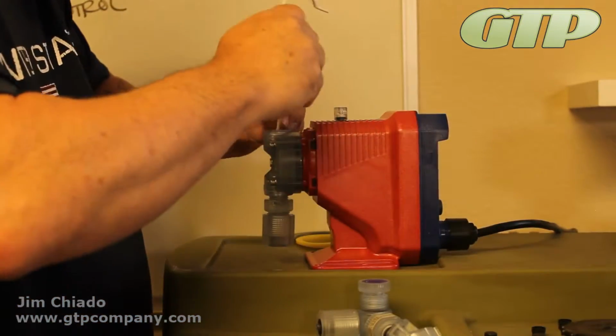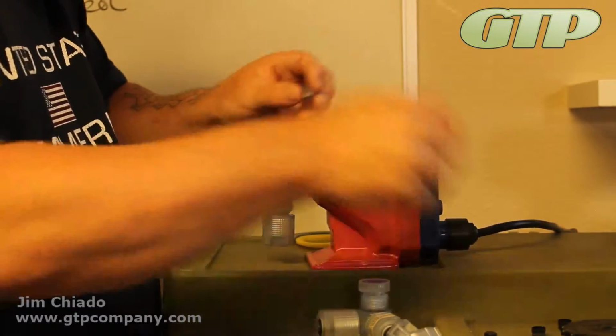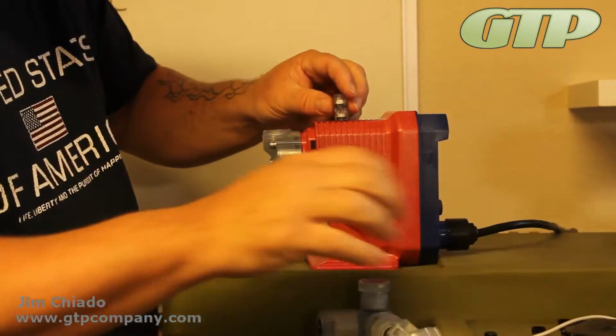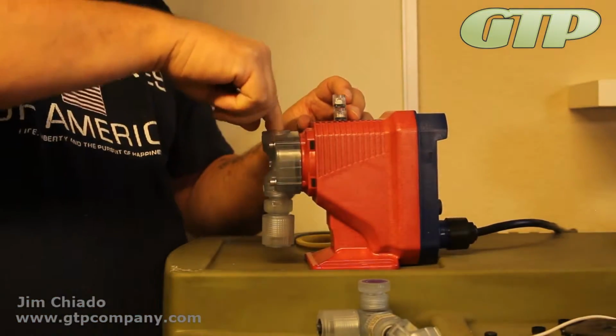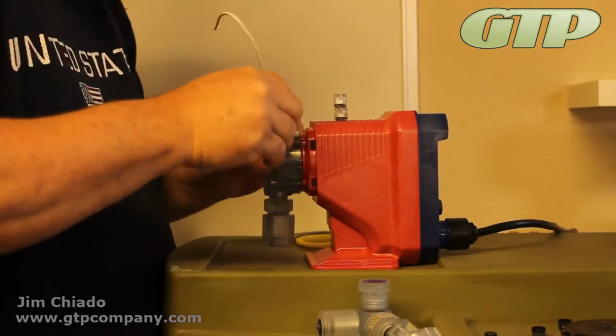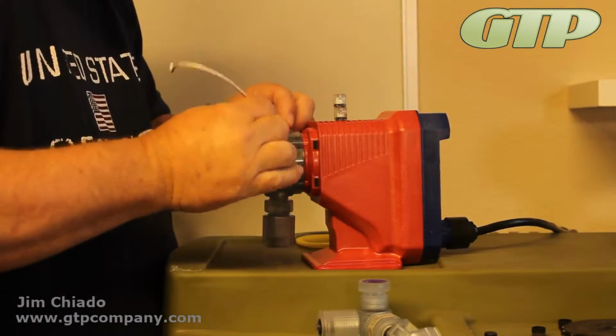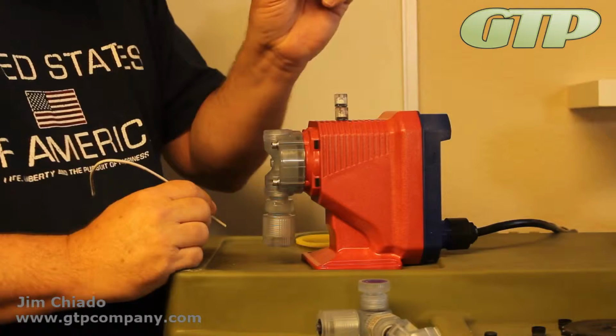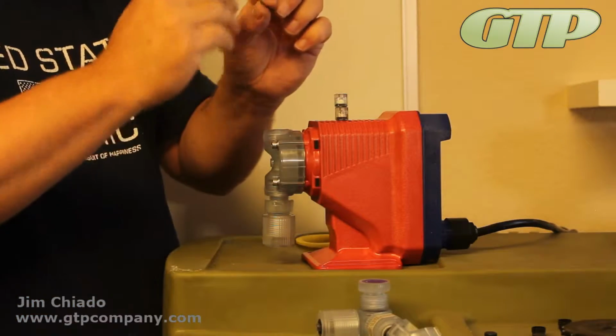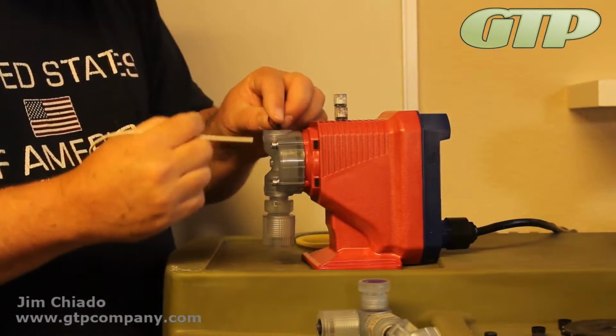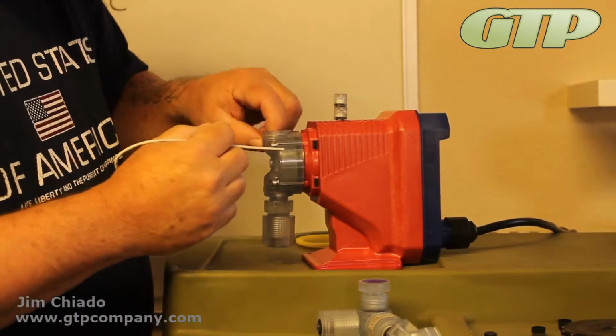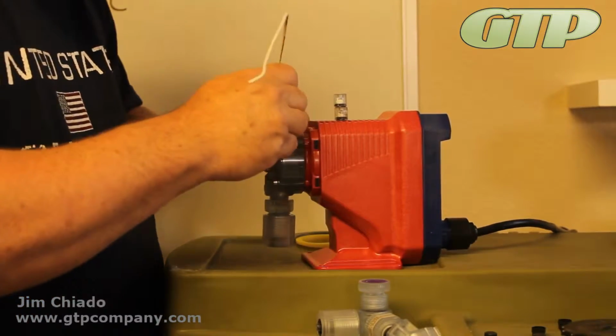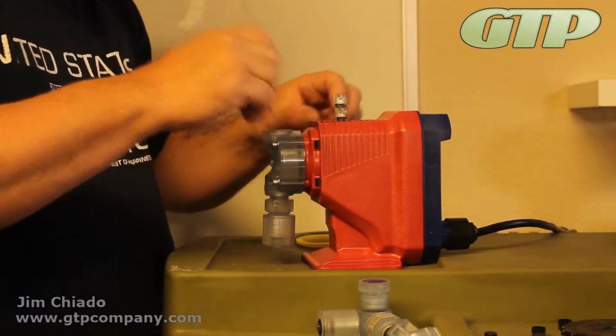These are always kind of tricky to get out of there. We're going to try and get one out. Okay, they'll always go like that. There's an O-ring inside here that you want to make sure is okay. Over time this does flatten out and elongate, so you want to replace those when you get a chance. That's really all the sealing mechanisms on top of this pump.